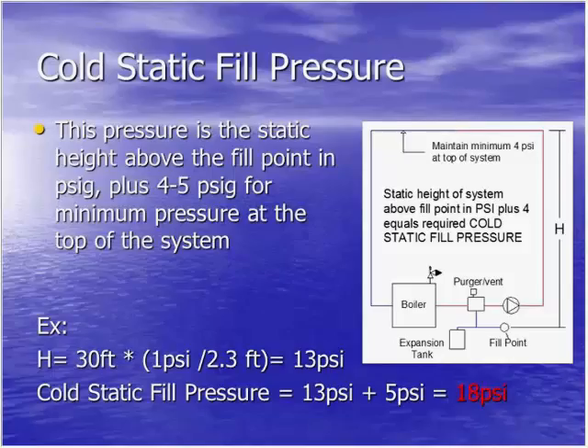So the cold static fill pressure is the height of the system from the fill point. So if you look at the little diagram there on the right side, you can see typically the boiler components are usually housed in a mechanical room in the basement somewhere. And then you've got pipes distributed throughout the building or house. And the highest point is, let's say in this instance, for example, 30 feet from the fill point.